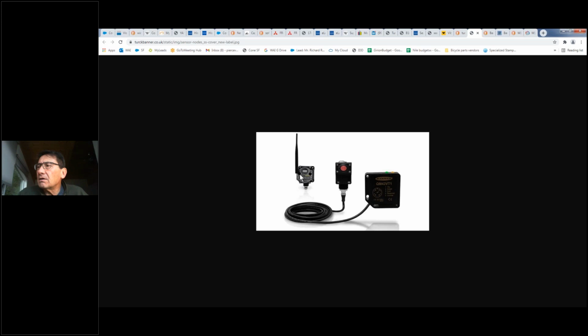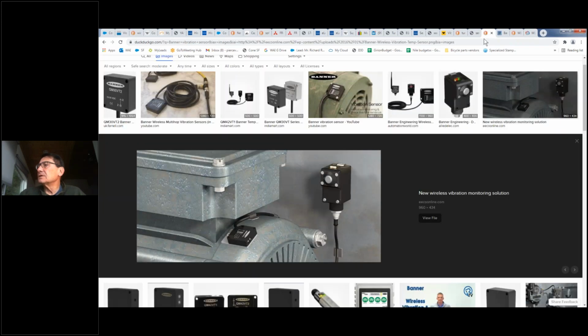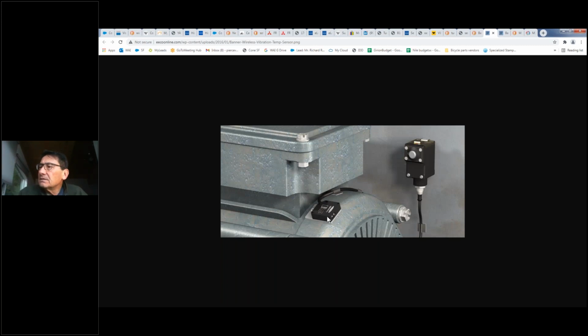So basically, you get an RF signal coming back to this receiver. By the way, these are all IP67 components. They're basically peel and stick, leave them outside. And that's that. Illustrative of how the sensor is installed. There you go. It's literally a peel and stick. And there's your transmitter. So very easy to install, and a great way to bring back the data to a place where you can figure out that you're about to have a failure and get out there and repair it before you do.